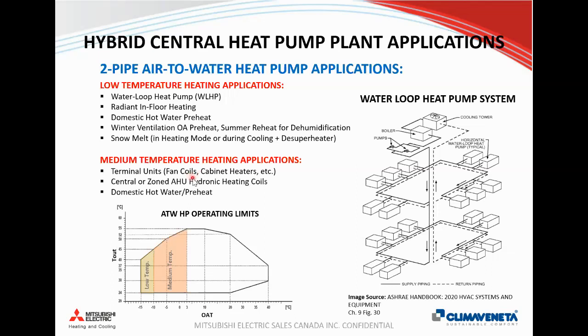And for retrofits, it's one thing if you're retrofitting a building to lower temperature and you have 200 fan coils in the building that need to be changed. That's obviously very intrusive. If you are talking about just air handling units that you're supplying heat to, it's much more economical to just change a coil designed around the heat pump parameters in an air handling unit. To pair that with the heat pump, that's a bit more feasible and more realistic from a financial point of view.